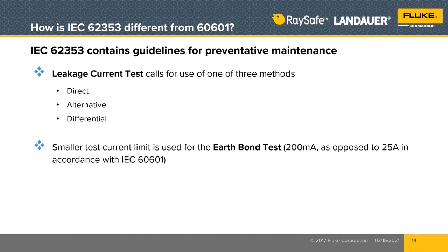And then you choose a method, direct, alternative, or differential, from the standard that is appropriate for use for that category of medical device. Now, as I said, you do that at your incoming inspection, your acceptance test, and then you stick with that decision about which test method. So if I pick direct when I get this new patient monitor, then ever after that, I have to continue to use the direct method. I don't choose direct one time and then the next year when I do the testing again, choose a different one. No, no, no, no. You pick the method you're going to use when you add that medical device into your inventory at incoming inspection, also called acceptance testing.